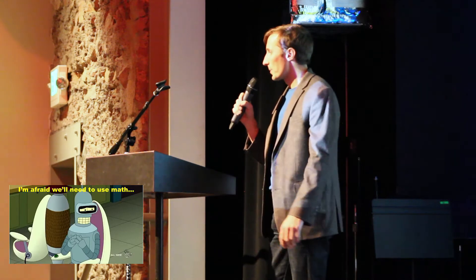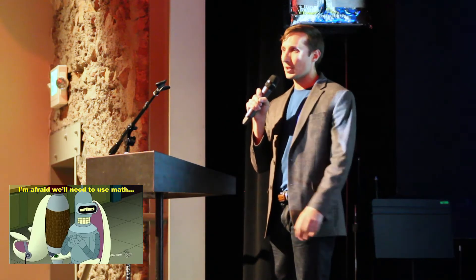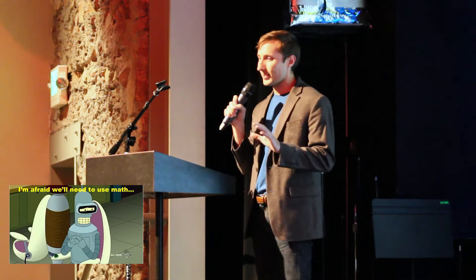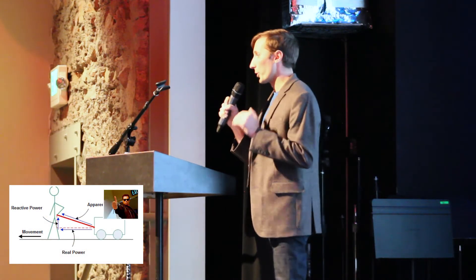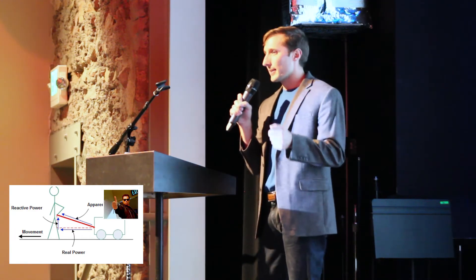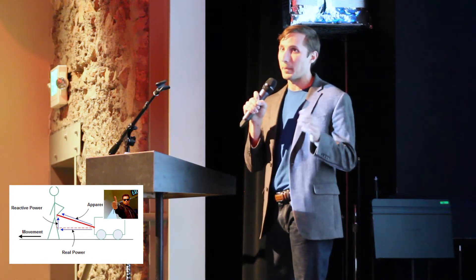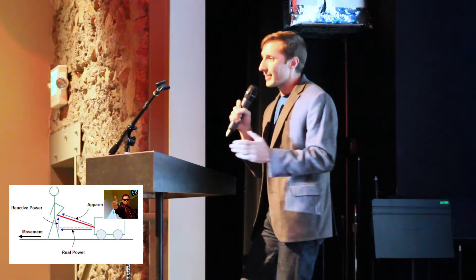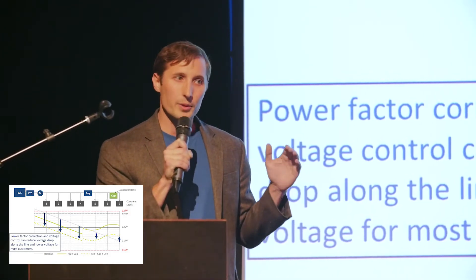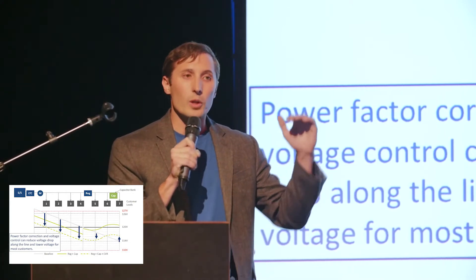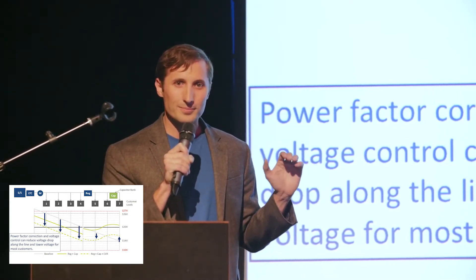So we've talked about voltage, we've talked about optimization — but I've glossed over the var part. If electrical engineering jibber-jabber makes your head hurt, you should stop listening for about 30 seconds. Alternating current has both real and reactive power — real being the beer, reactive being the head. But that graphic is pretty misleading. Think of a wagon: moving the wagon forward is the real power, and lifting the handle, while necessary, does not move the wagon forward — that's the reactive part. So power factor correction and var optimization is moving the wagon forward and reducing the height of the handle. We use capacitors and regulators to flatten the voltage profile, and then we can actually lower voltage for everyone.